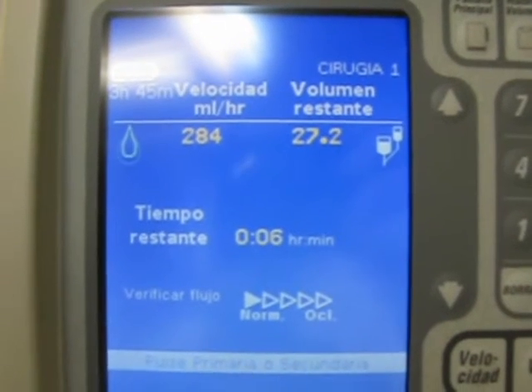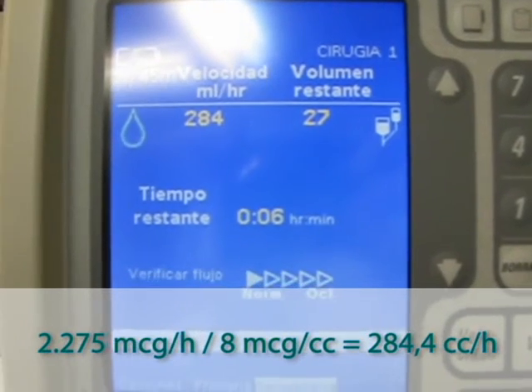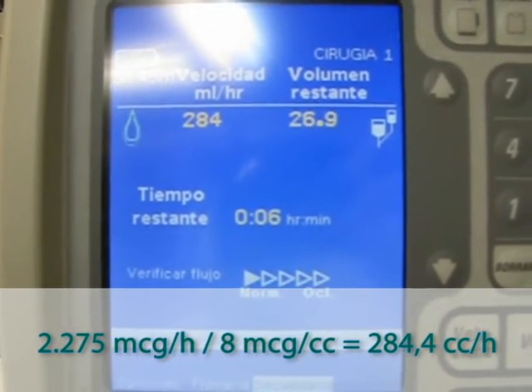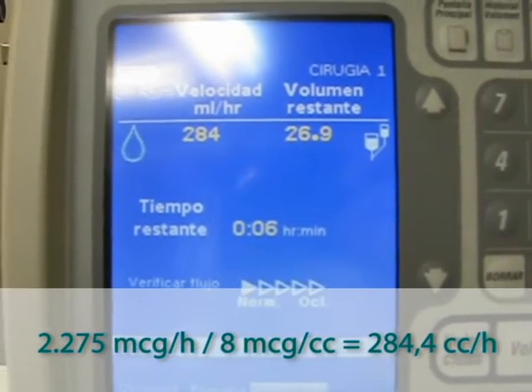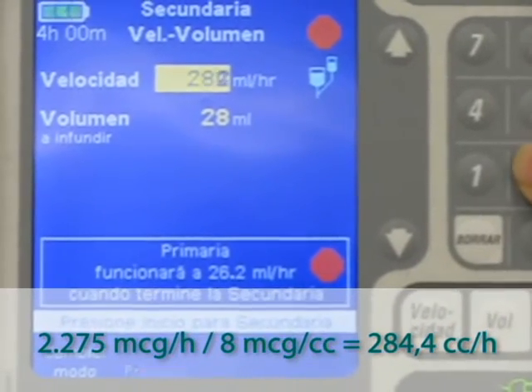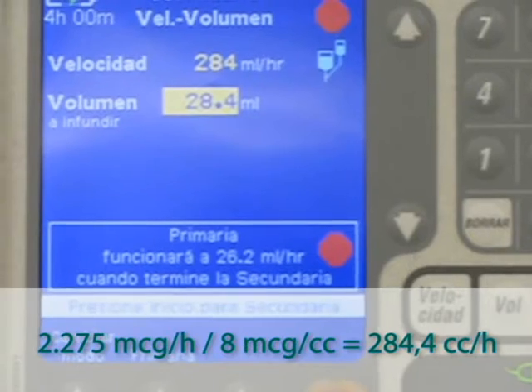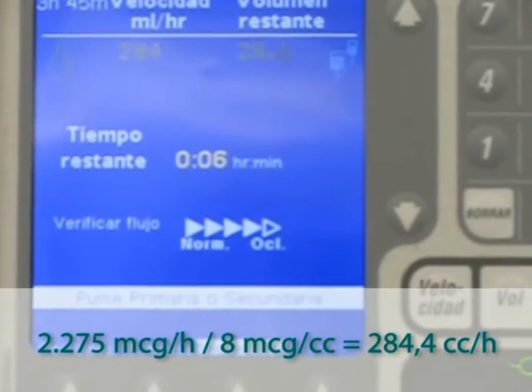For example: 35 micrograms × 65 kilograms per hour equals 2,275 micrograms per hour. This value is divided by 8 micrograms per cc (the concentration being used), giving 284.4 cc per hour. Since this concentration is needed for only the 10th part of an hour — that is, 6 minutes — only the 10th part of the 1-hour volume is required. Therefore, 28.4 cc is the volume to pass in 6 minutes, and the pump is programmed in secondary infusion mode: rate 284 milliliters per hour, volume to infuse 28.4 milliliters. These relations are followed in all cases.